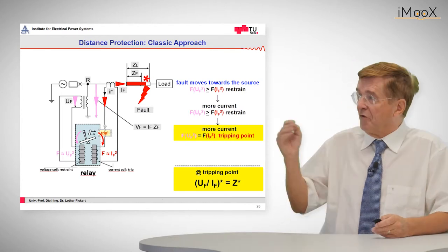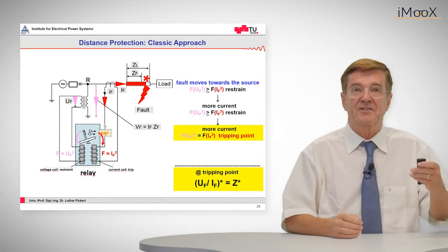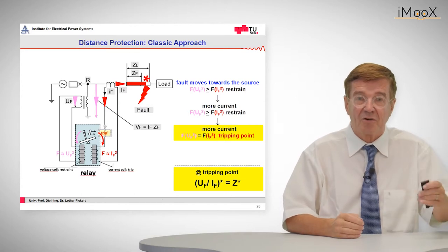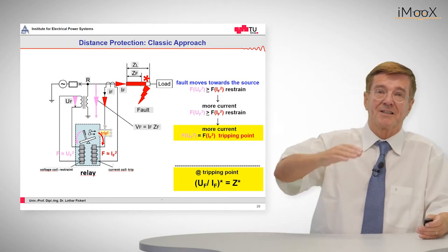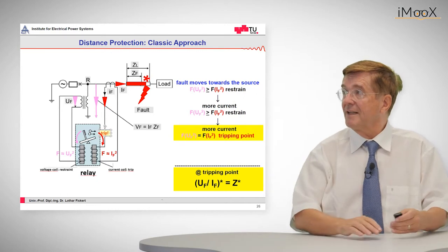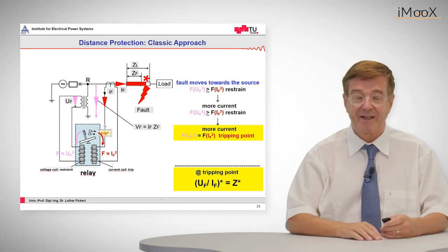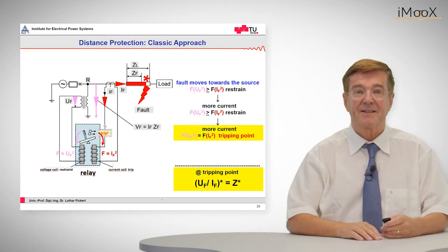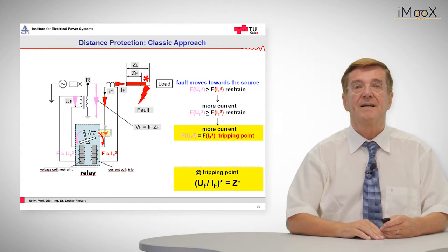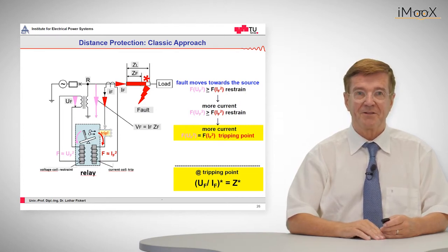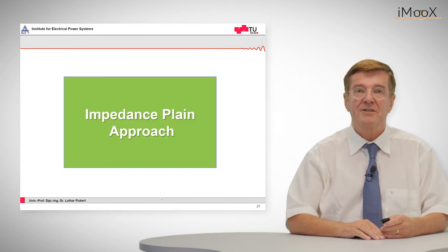And if the fault moves in further, then the residual voltage, the restraining force, gets even lower and the currents will get up. So in this red area we have a trip area and this is the tripping area and by this means such a relay can discriminate between the trip zone and the restraint zone.